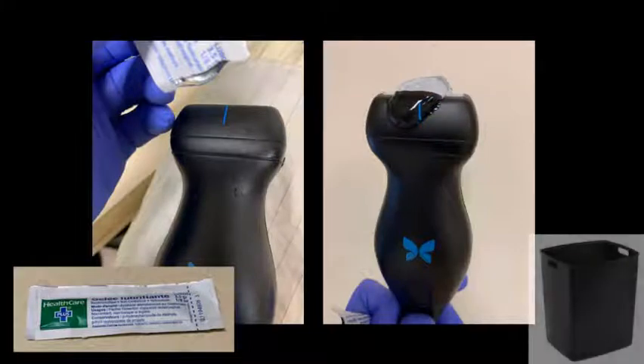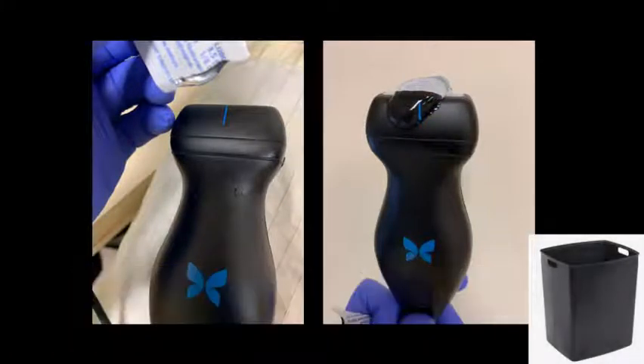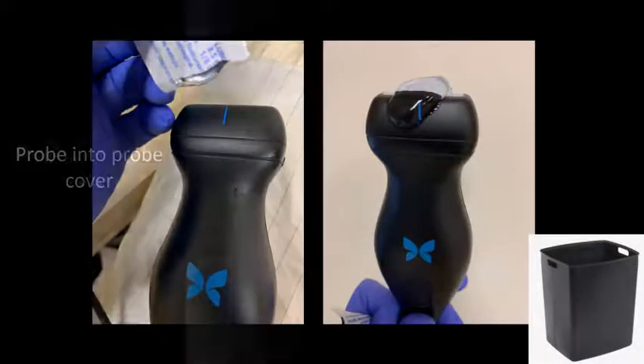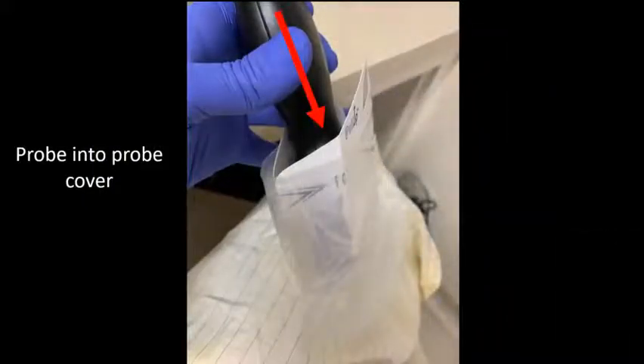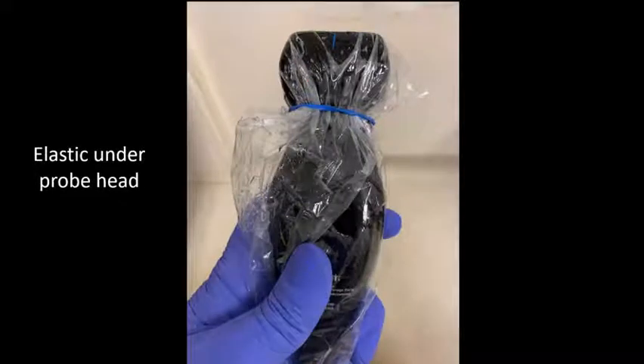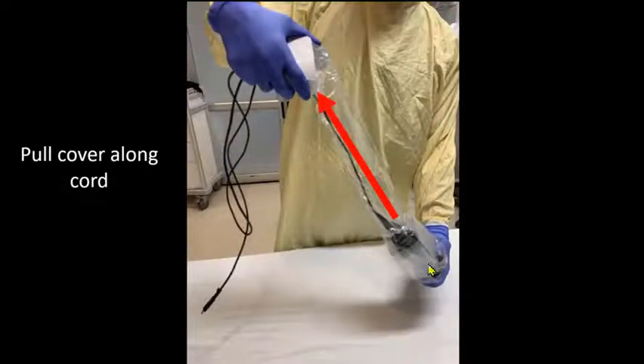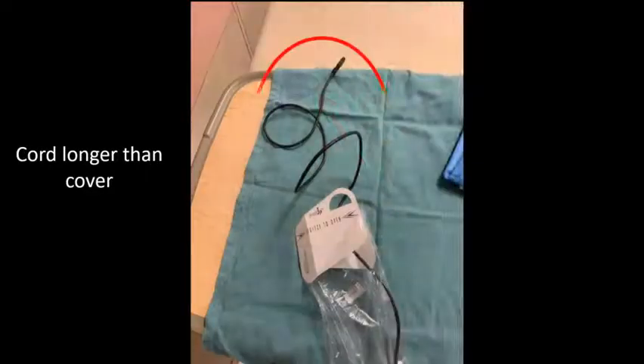Then you'll put some gel on the probe head and chuck the package into the garbage. Then you'll direct the probe into the probe cover. And once the probe is fully into the probe cover, then you'll place an elastic just under the probe head. Once that's done, you'll pull the probe cover along the cord as you see here, and you'll pull the probe cover fully out to length. Now what you'll notice is that the cord is longer than the probe cover.